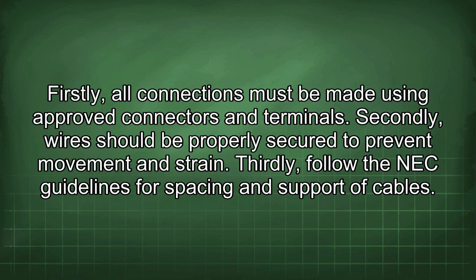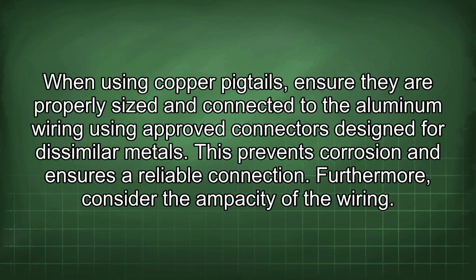Firstly, all connections must be made using approved connectors and terminals. Secondly, wires should be properly secured to prevent movement and strain. Thirdly, follow the NEC guidelines for spacing and support of cables. When using copper pigtails, ensure they are properly sized and connected to the aluminum wiring using approved connectors designed for dissimilar metals. This prevents corrosion and ensures a reliable connection.